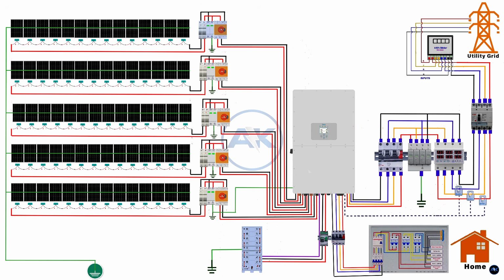For anyone considering a system like this, remember the key takeaways. 1. Plan meticulously. Site assessment, permits, and string design cannot be rushed. 2. Safety is absolute. HVDC and three-phase AC are no joke. Use qualified professionals. 3. Configuration is key. The hardware is just metal without the correct software setup, especially for zero export mode. This system isn't just an expense, it's a long-term investment that takes a major operational cost, energy, and brings it under control.